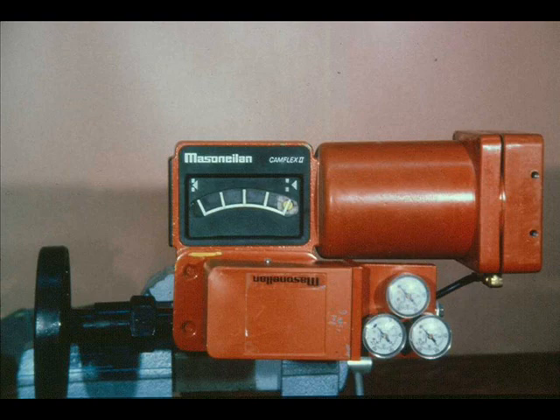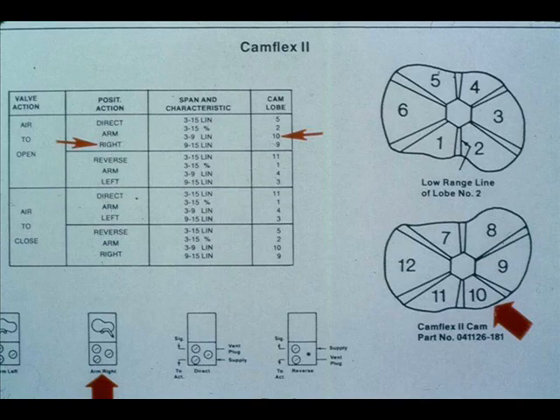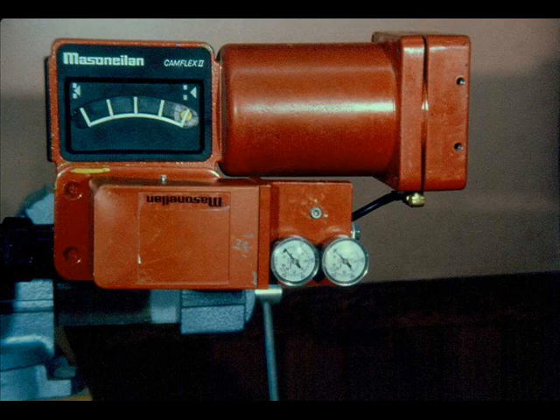The next example of calibrating the 4600 positioner will be on an air-to-close Camflex 2 valve. The positioner will be split ranged, reverse acting, and will give the valve a linear characteristic with 3 to 9 PSIG input. According to the instruction manual, the lever arm will be mounted on the right side and CAM lobe 10 will be used. The supply and exhaust have to be interchanged. Because the supply and exhaust have been interchanged, the supply gauge does not measure the supply pressure and must be removed and plugged to keep from confusing others.